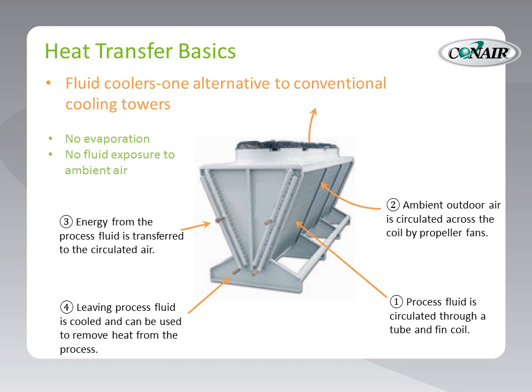So what alternatives do we have for evaporative cooling towers? Fluid coolers, also known as dry coolers, could be used. Processed fluid is circulated through the tube and fin coils in the cooler, and fans circulate ambient air over the coil to transfer energy from the coil to the air. The cooled process fluid is then returned to the process. Very simple. And fluid coolers use no water for evaporation.